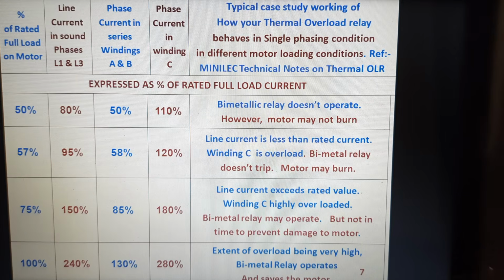It's a typical case study on the given thermal overload relay, how it behaves in the single phasing condition. At 50% of the motor loading, the phase current in C is around 110%. The bimetallic relay does not operate. The motor may or may not burn in this condition. At 57%, you can see the phase current in this C winding has gone to 120%. Here also the bimetal thermal relay does not trip and the motor may burn out.